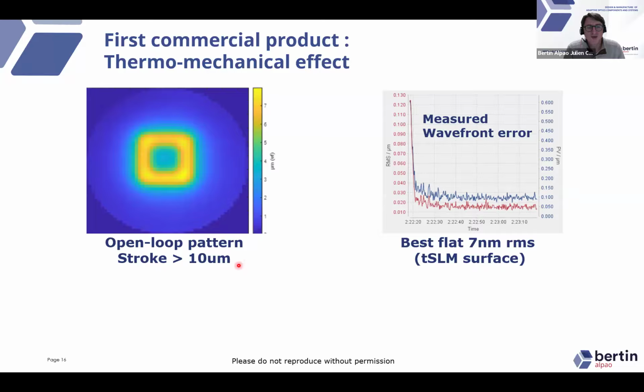The next important part for this kind of device is, okay, what is the best optical quality you can obtain? In this case, you have to operate in closed loop. We have a wavefront sensor, like the one measuring this pattern, and we use it to minimize the wavefront map and to have the device as flat as possible. This is a temporal response, for the PV and RMS wavefront errors that we measure. We start with the bias shape of the device, which is 100 or 200 nanometers RMS across the pupil. When we close the loop, in a few iterations we can slowly reduce this error, and the best flat we can obtain, giving you an idea of the best optical quality, is 7 nanometers RMS.